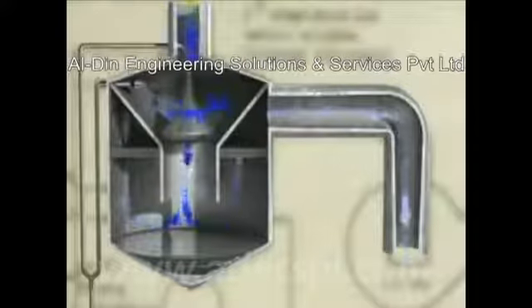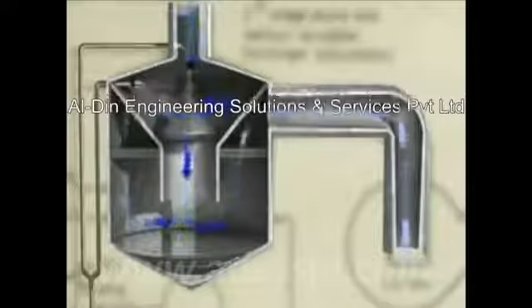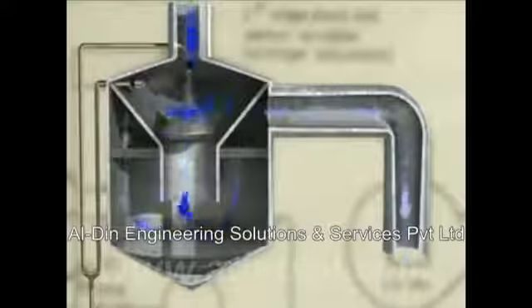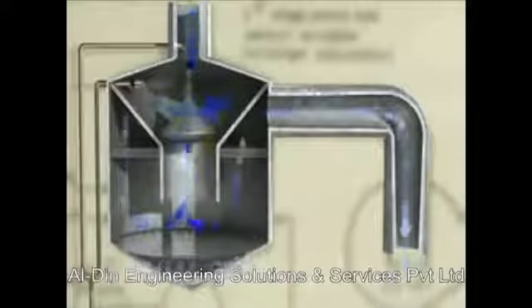Our plants are equipped with air quality control systems to remove sulfur dioxide and particulates called fly ash. Fly ash is removed by a mechanical process, and sulfur dioxide is removed with a chemical reaction using lime. These processes take place in large ductwork scrubber trains located between a unit's boiler and its chimney. Boiler gases pass through scrubbing vessels and are sprayed with slurry, a mixture of water and lime. The sulfur dioxide particles and other pollutants are absorbed by the slurry and fall to the bottom of the vessels. A fan releases the cleansed gases through the chimney.